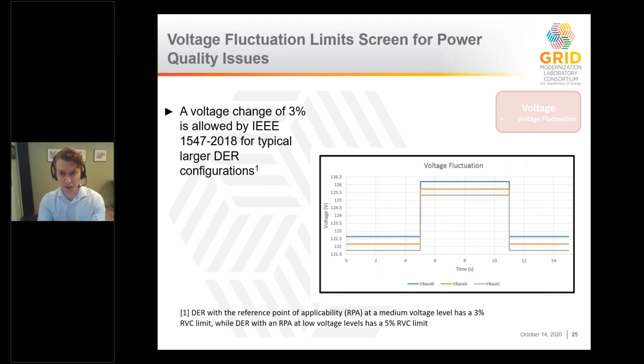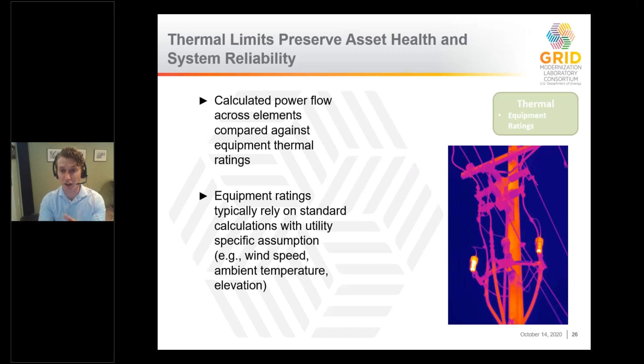Thinking of capacity constraints, thermal limits really drive them — the amount of power that can be pushed across a conductor. A limit may be reached in hosting capacity where the level of reverse power flow starts to encroach upon equipment rating limits. This is another key criteria for hosting capacity.